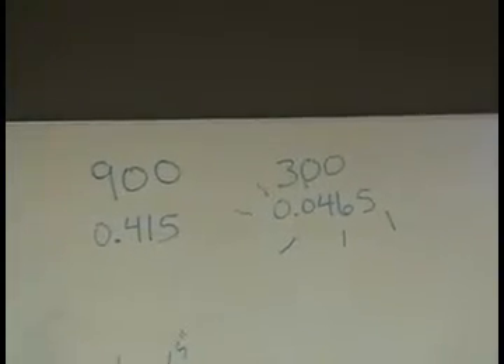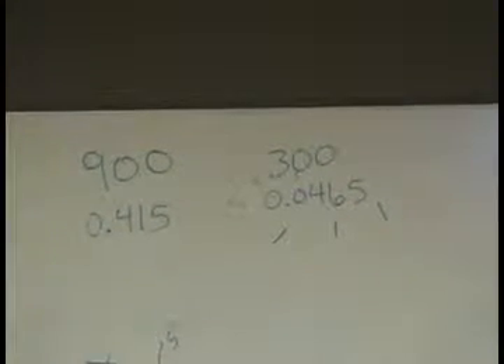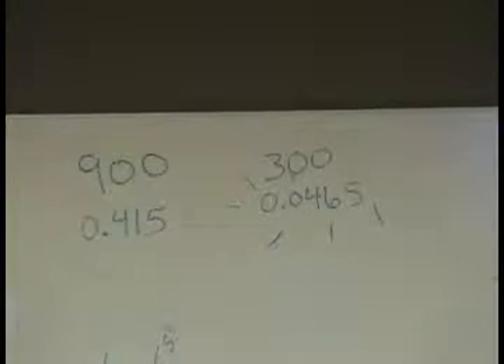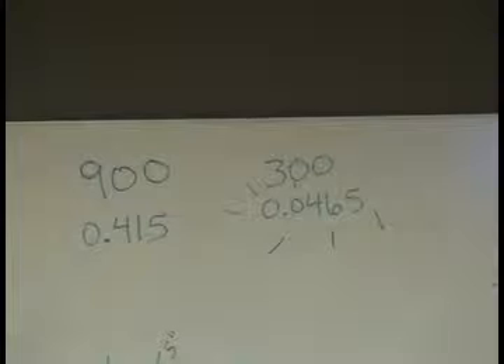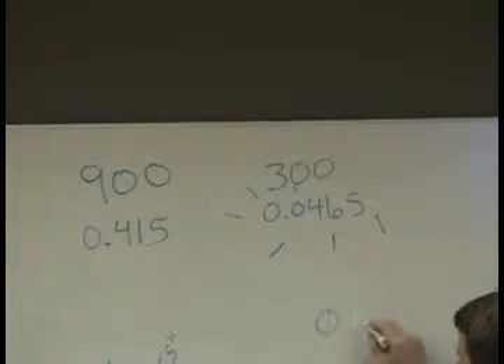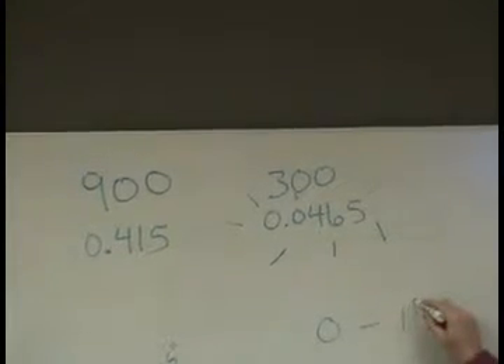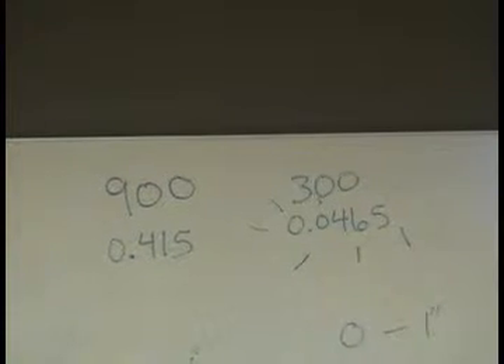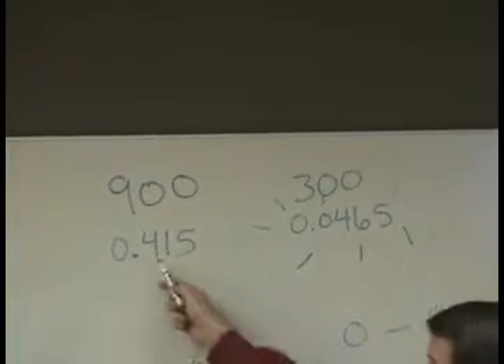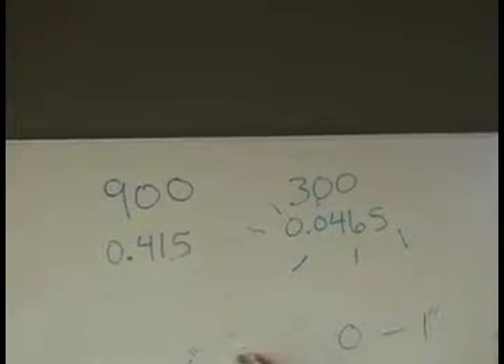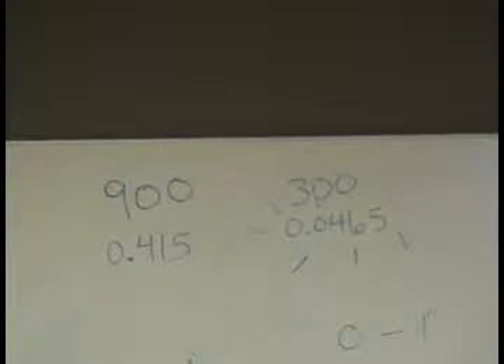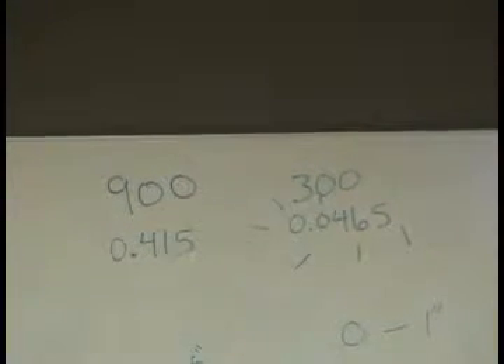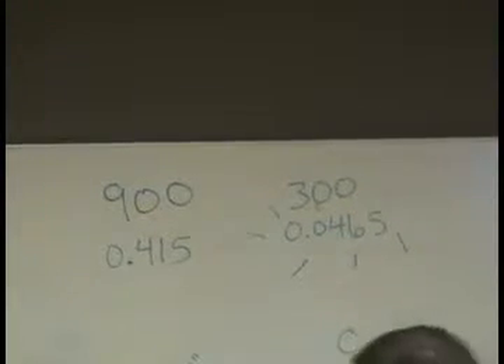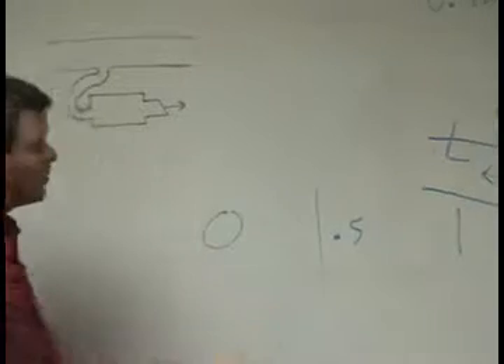The Andover has the onboard airflow sensor on the 850. It's only accurate to 50 thousandths inches of water column. It is a 0 to 1 inch sensor. And when we're trying to measure 0.415, you know, we're 40% up into the scale. On a 0 to 1 scale, we're measuring right there, off in the middle, and we've probably got real good accuracy.